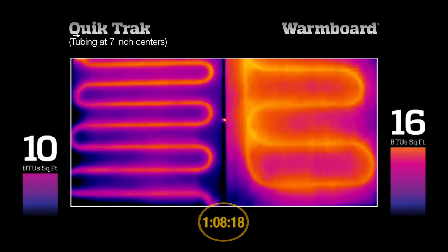After an hour and 9 minutes, Quik Trak reaches the 10 BTU output, although surface temperatures are quite uneven. In that same amount of time, WarmBoard is delivering 16 BTUs with more even heat.